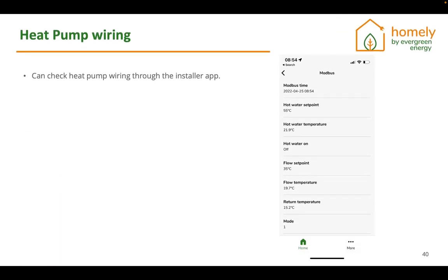A few other things just at the point of the installation is to check the wiring of the heat pump. Once you've followed all the steps in the installer app, installing a Homely, click on the Modbus menu on the installation that you've just done and see whether you can see all the data coming back from the heat pump. This is just to make sure that the heat pump and the Homely hub are actually communicating over Modbus. So Modbus is our communication with the heat pump. It's two cables through which we can actually see all of this information.